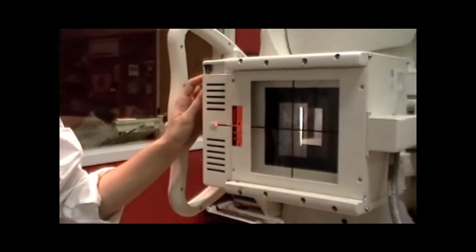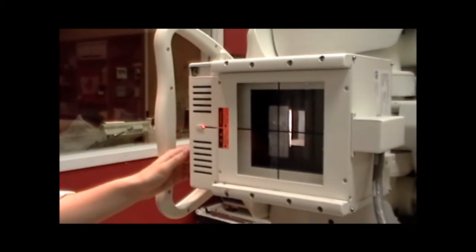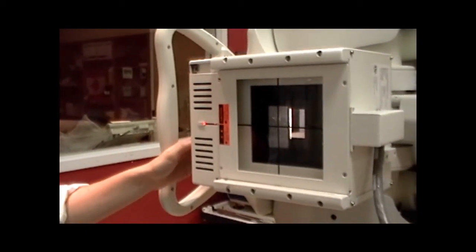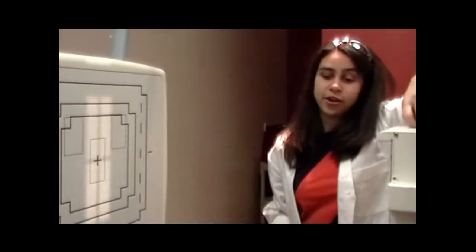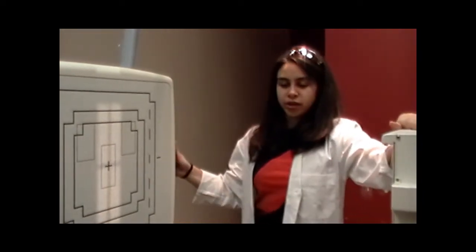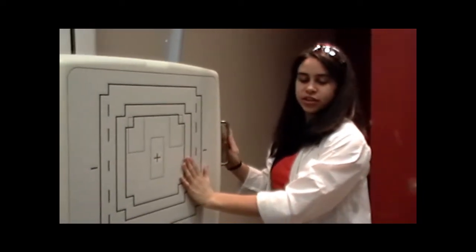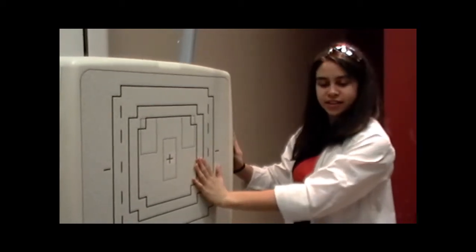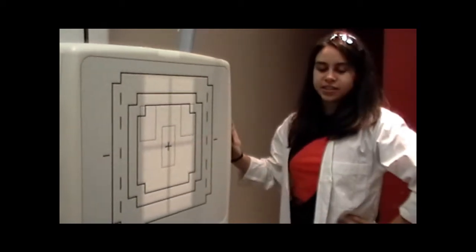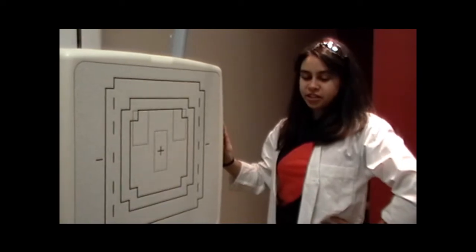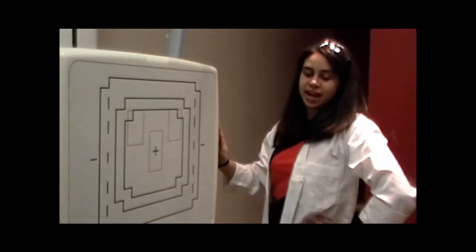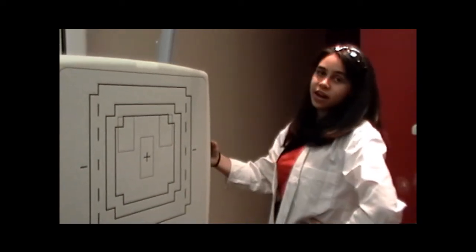They're comprised of 2 to 3 lead shutters that are individually movable, making the beam turn from a circle to a square or rectangle. It is the most sophisticated and useful in radiography. There's a light projected from the tube housing, and it shows where the beam will hit. When the image receptor is inserted, collimators can move to the size of the image receptor. This is known as positive beam limitation and reduces the patient dose by ensuring you're not exposing an anatomic part that won't end up on the IR.